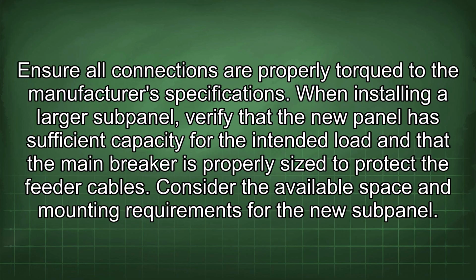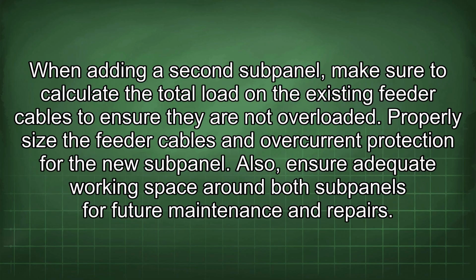Ensure all connections are properly torqued to the manufacturer's specifications. When installing a larger subpanel, verify that the new panel has sufficient capacity for the intended load and that the main breaker is properly sized to protect the feeder cables. Consider the available space and mounting requirements for the new subpanel. When adding a second subpanel, make sure to calculate the total load on the existing feeder cables to ensure they are not overloaded. Properly size the feeder cables and overcurrent protection for the new subpanel.